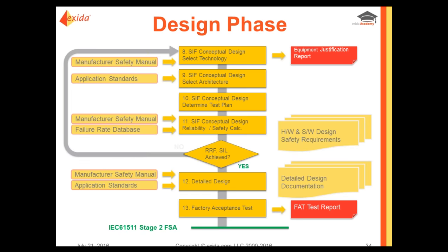Once the technology is chosen, often you can do a redundant configuration or redundant architectures based on the experience in the safety instrumented design. There are several different architectures that can be used depending on performance of the individual components needed for the system. You can look at a 1-out-of-1 system, or if you need to add a hardware fault tolerance or a redundancy, you can look at a 1-out-of-2 system, or a 2-out-of-3, or you can even look at systems with automatic diagnostics. Say a 1-out-of-2D would be diagnostics. If you have an architecture such as a 2-out-of-3 configuration, what that means is there are three elements present, and two of those devices must indicate a trip in order for that trip to be signaled.